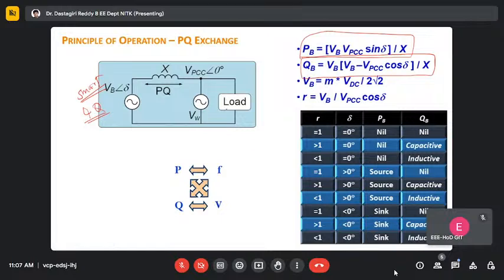The problem is, if it is a machine-based power system, a machine-based generation system, your P is linked to frequency and your Q is linked to voltage. Everybody knows this. But when you have converter-based generation, like a voltage source converter, this relation is not valid. Both P and Q are still linked to the voltage. Your frequency is decided by your modulation index, so that never gets affected. So that is the tricky part: when you bring in machine-based grids and converter-based grids, you can't strictly follow the so-called V-Q or voltage-linked-to-reactive-power and active-power-linked-to-frequency rule. That is only for machine based generations, not for converter based generations.